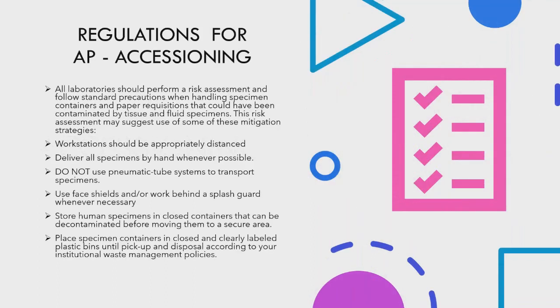For accessioning, workstations tend to be close together — distance them as best you can. Specimens coming in from COVID floors should be sent down by hand, not through pneumatic tube systems, as breakage in the tube system could be catastrophic to disinfect. Double-container specimens, especially glass containers like pleural fluid, so that if dropped, a secondary container catches it.